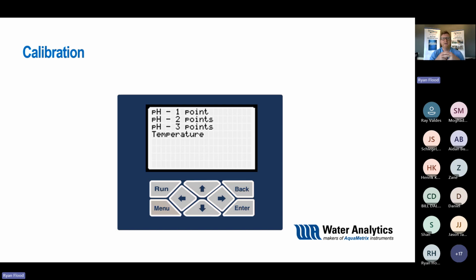For the sake of the demo today, I'm just going to do the 2 point calibration. That's really the preferred methodology when it comes to pH calibration. You can do a 1 point calibration. It's not highly recommended. Some people will do it, but really the majority of installs and the most recommended approach is going to be your 2 point calibration. If you want that extra precision, then go ahead with your nice 3 point calibration, right? Again, we offer 3 different calibration standards, 4, 7, and 10, so your 3 point calibration can easily be done with those. All it takes is just the extra time to do that last solution, which you won't see today. I'll walk through with just 2 standards and show you just how simple that will be.